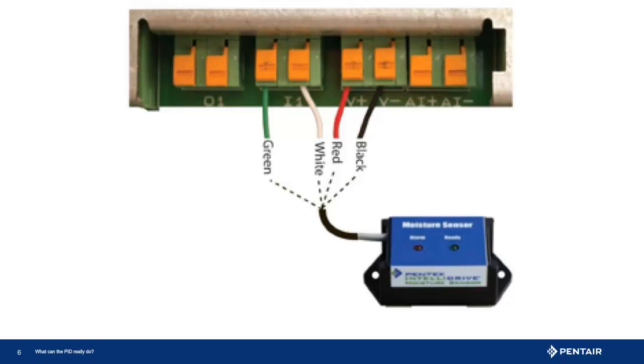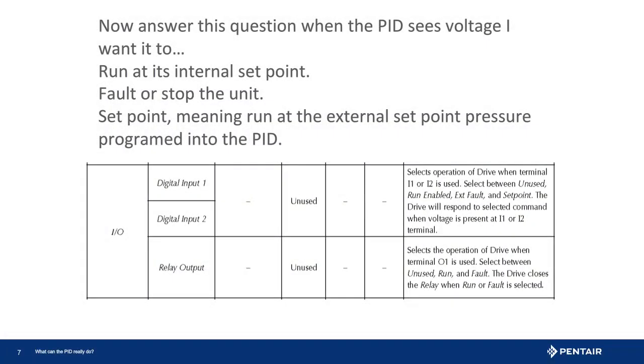Now that is only half of the setup. Now we need to answer a simple question. When the control completes the circuit to the input passing the voltage, what do we want the drive to do? Here is a very typical control. Our water detection safety. This unit is placed on the floor to detect a potential water leak. When water creates a bridge completing the circuit, we want the IntelliDrive to? Well, in this case, I would want the control to turn off the pump.